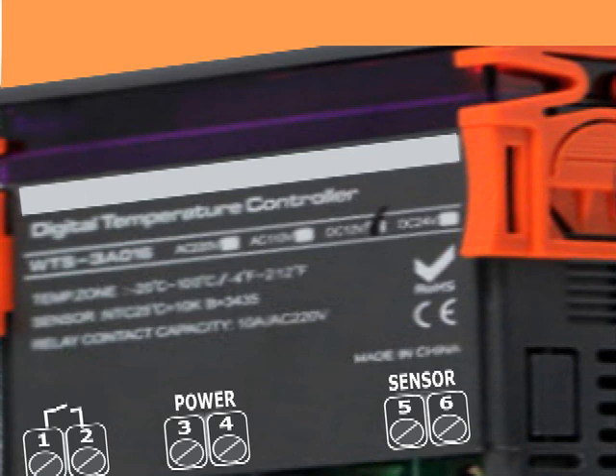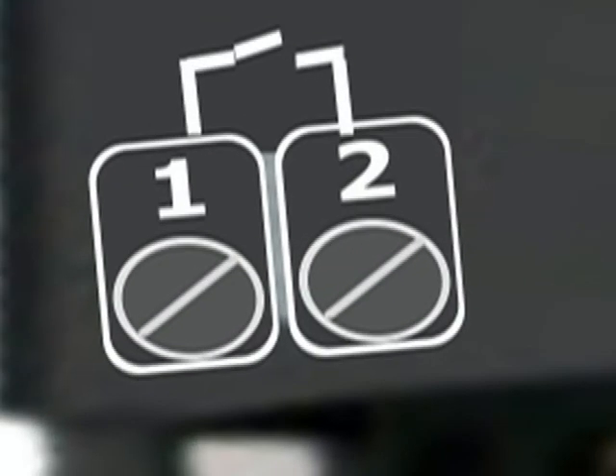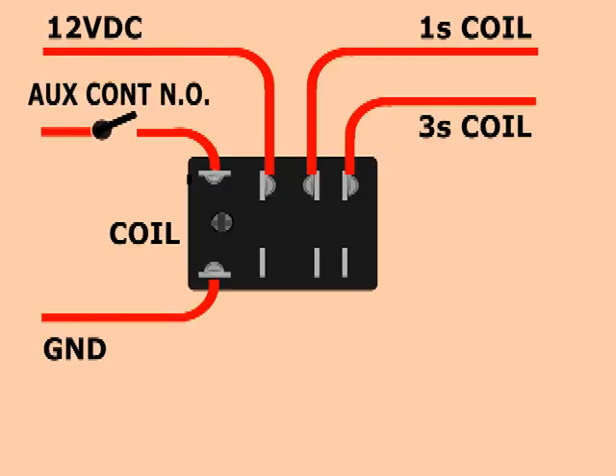Then we bought a simple, inexpensive thermostat that would activate the reset when the right temperature was reached. Since this cheap thermostat, which we will call auxiliary, only had a normally open contact output, a relay had to be added to make a normally closed contact available.